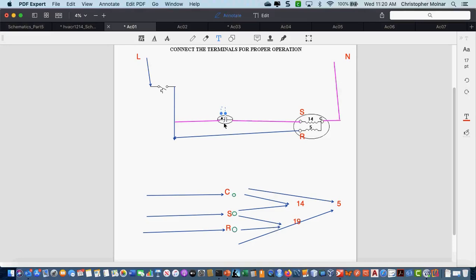Now, a run capacitor with a dot and without any switching device, if it's straight to start, we know it's a run capacitor. There's two different types of capacitors. Again, for those who haven't had anything with motors before, we spend a lot more time on this, but just as an overview right now, you have a start capacitor and a run capacitor. The run capacitor most often is drawn with a dot. That's part of the capacitor drawing.